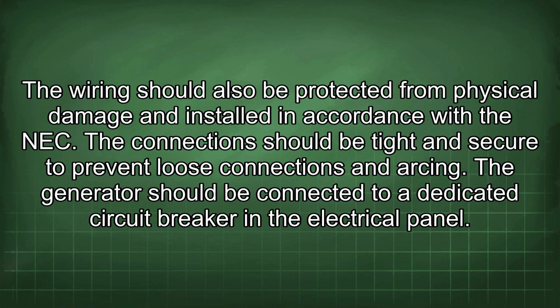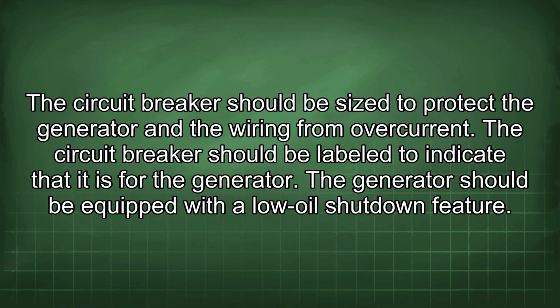The generator should be connected to a dedicated circuit breaker in the electrical panel. The circuit breaker should be sized to protect the generator and the wiring from overcurrent. The circuit breaker should be labeled to indicate that it is for the generator.